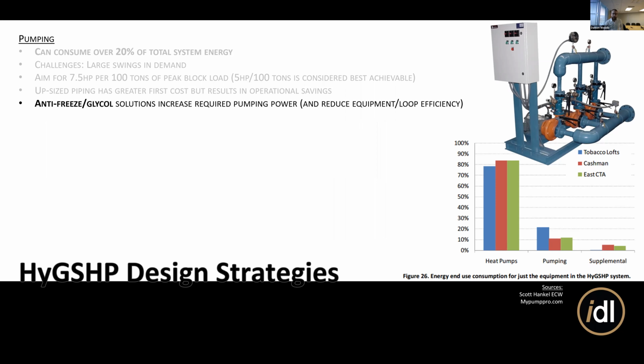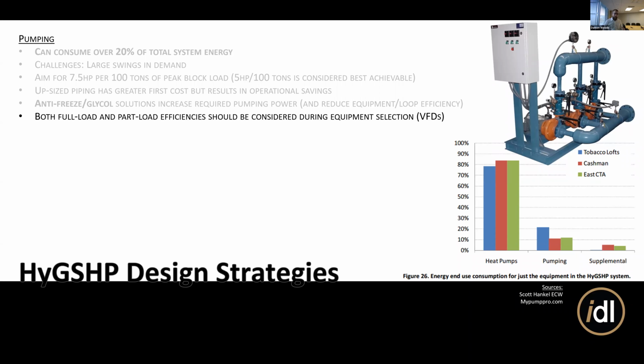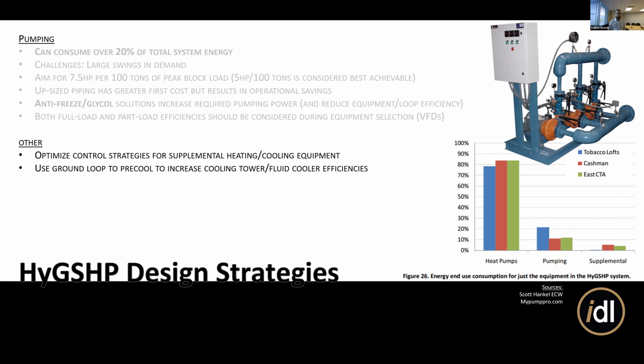Yeah, I already mentioned the antifreeze, but look at both full load and part load efficiencies. If these pumps are sized for one particular load and instead they're operating somewhere else on the pump curve, they might be in a really inefficient region. So this really comes down to the design of the system and why I think hourly simulation is really important, to make sure that you're accounting for how these are actually going to be used all year round at a variety of different conditions.